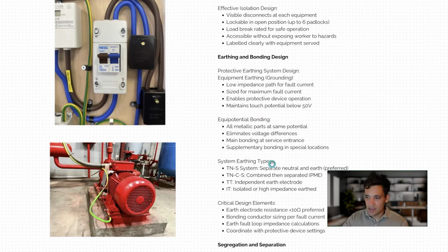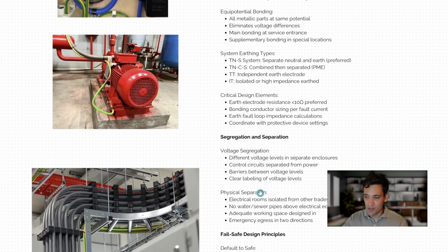In addition to isolation points and earthing, another critical principle of electrical design is segregation and separation. Different voltage levels, power, comms, everything should be separate, clearly labeled, and everything should be easily isolated. So you could isolate high voltage without impacting low voltage, which means things need to run in separate cable trays through separate conduits. You need physical separation between high voltage equipment, low voltage equipment in separate rooms.